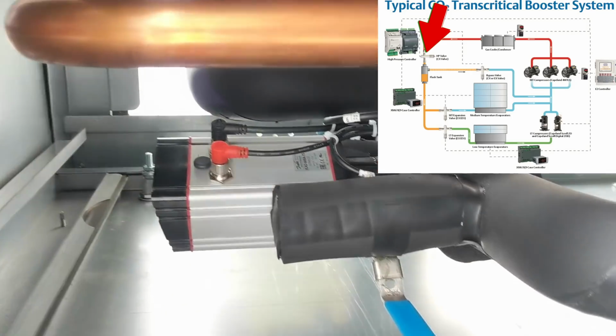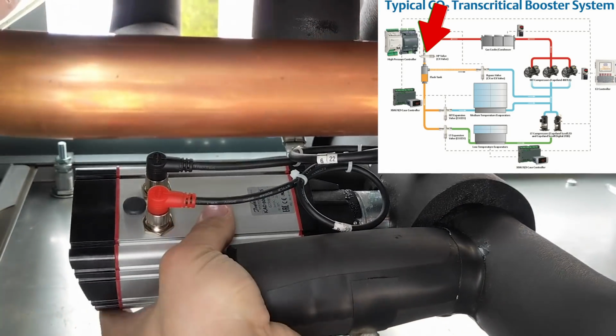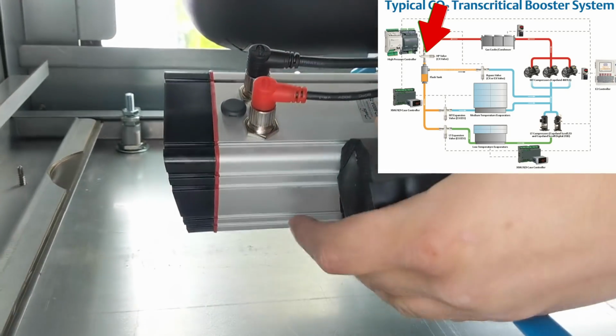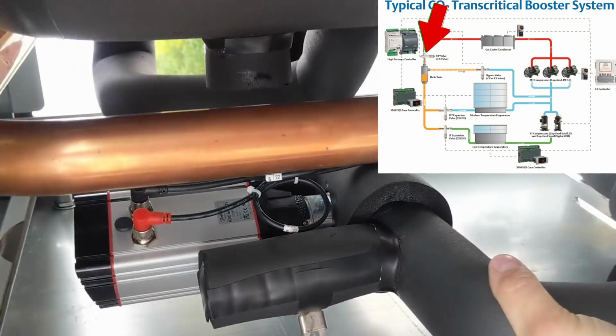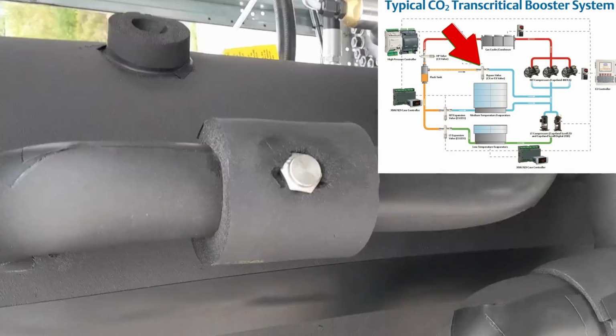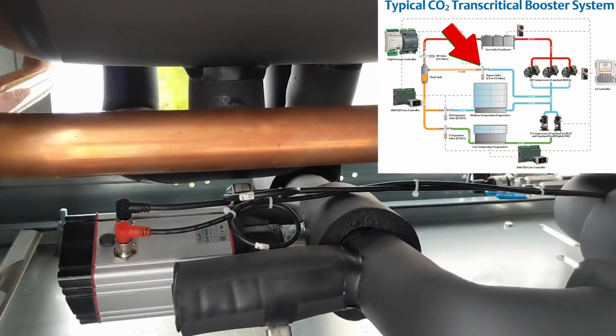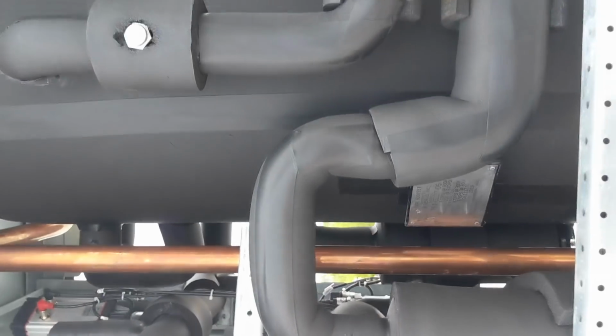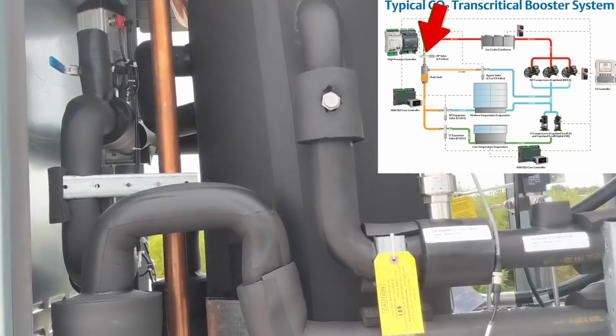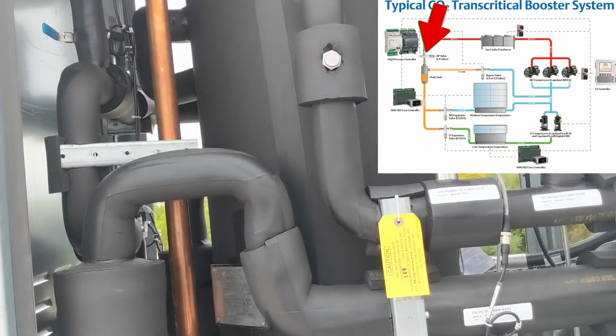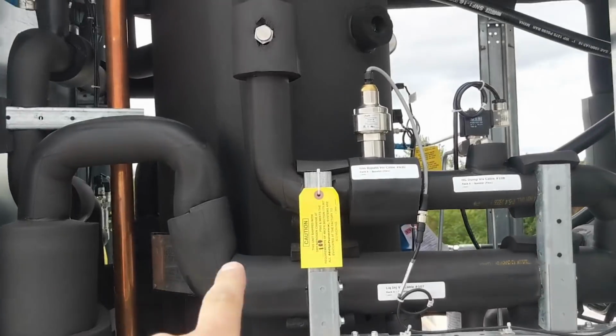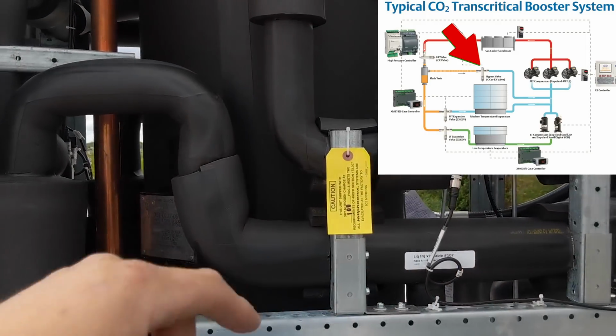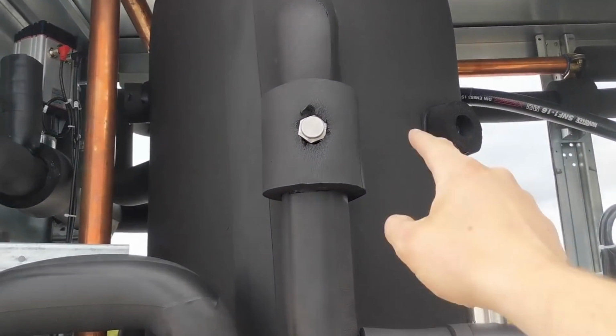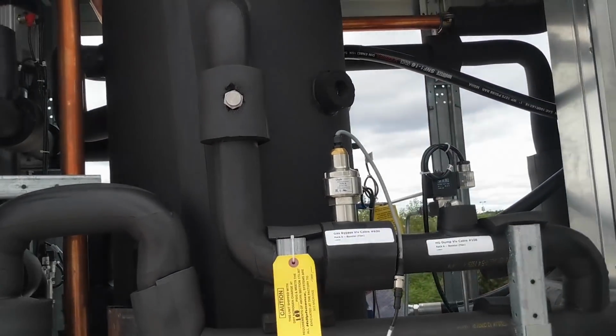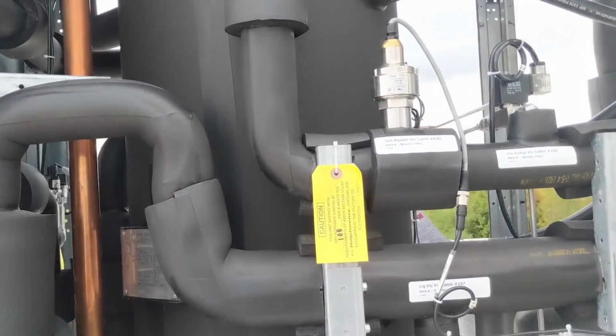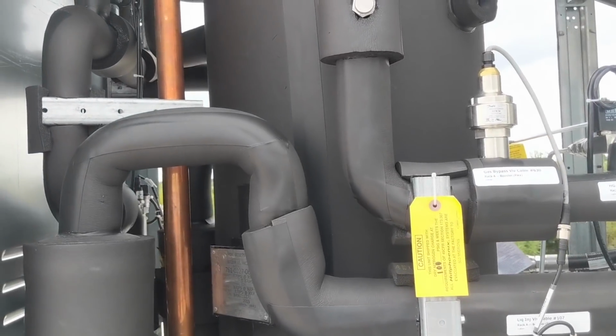We're going to hit our high pressure regulating valve. So we have this valve right here, this Danfoss valve. It's a high pressure regulating valve. And right here is our flash gas bypass. It comes off the top of the receiver. What we're doing with these 2 valves, they're accomplishing 2 things. They're working together. Your high pressure regulating valve is constantly going to be holding back gas in the gas cooler, and your flash tank bypass valve is going to constantly be venting off the top of the receiver / vessel into the medium temp suction header in order to condense the CO2 back down.